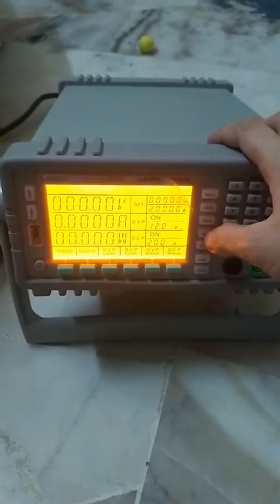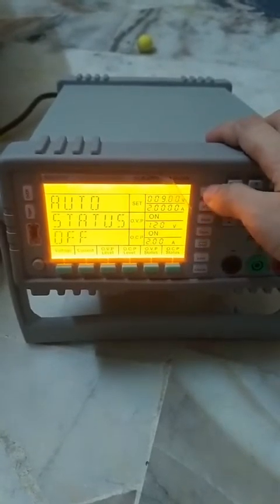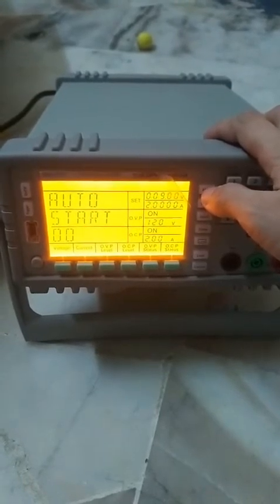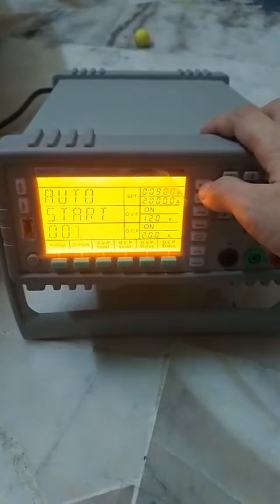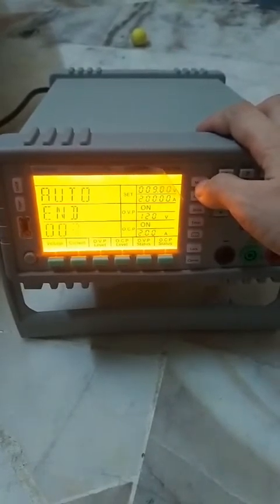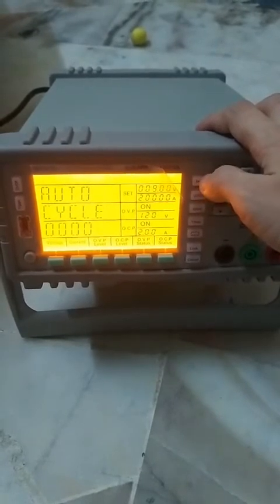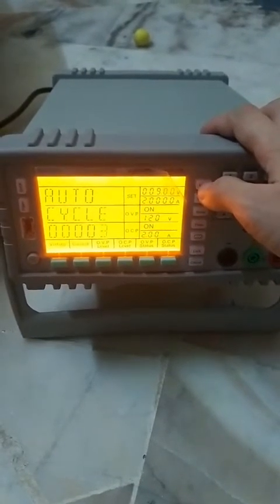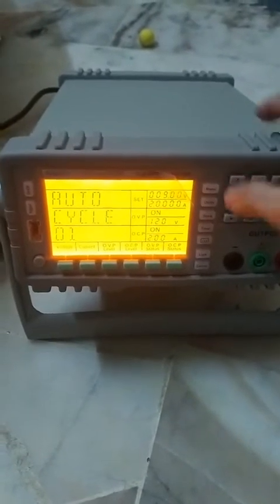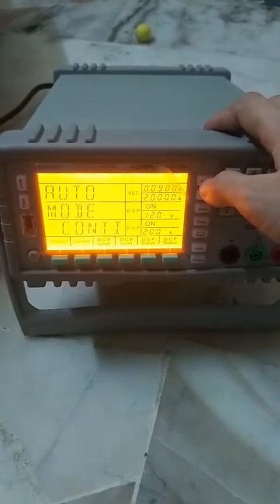At this moment you need to let the program output in a preset mode. So you click timer. Then set the auto status as off. You set auto start from the first step, you select 1. Auto end at the third. Set the auto cycling time. If you would like the program to be repeated 3 times, you set 3. If you would like the program not to repeat, you just set 1. Enter.